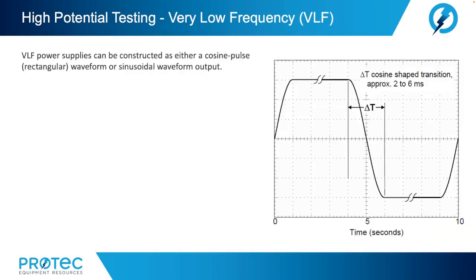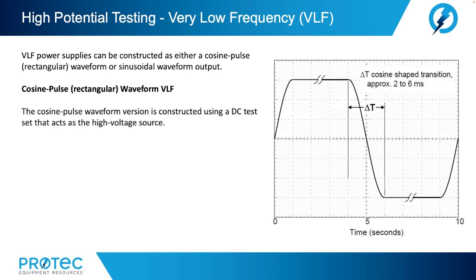Now, VLF power supplies can be constructed as either a cosine pulse or rectangular waveform, or they can be constructed as a sinusoidal waveform output. Let's first look at that cosine pulse or the rectangular waveform VLF. The cosine pulse waveform version is constructed using a DC test set that acts as the high voltage source. A DC to AC converter then changes the DC voltage to the VLF AC test signal.